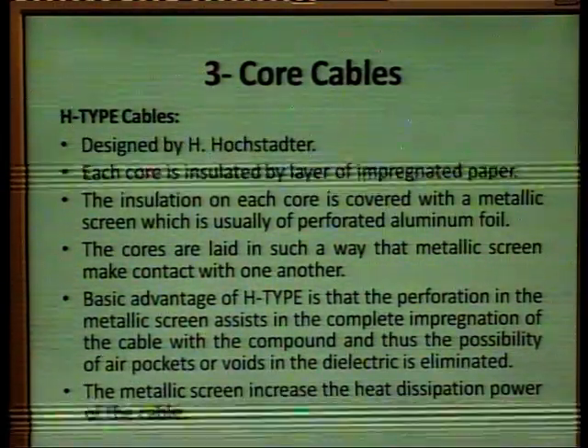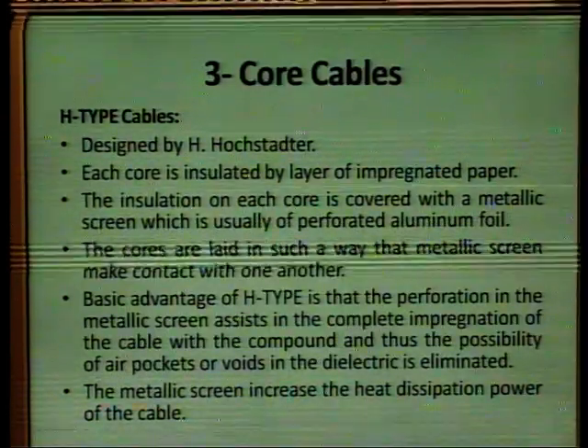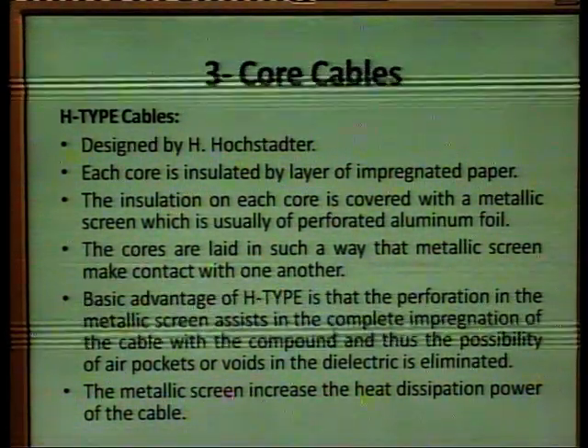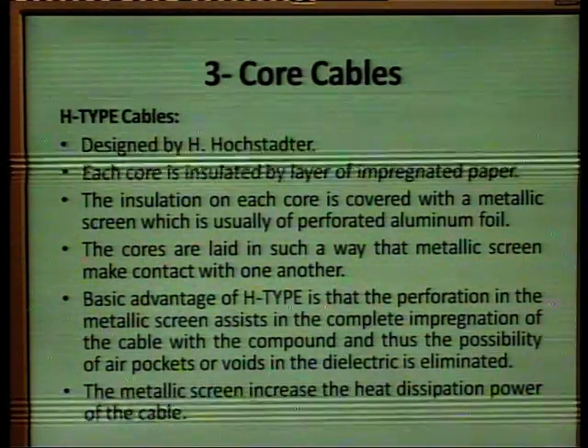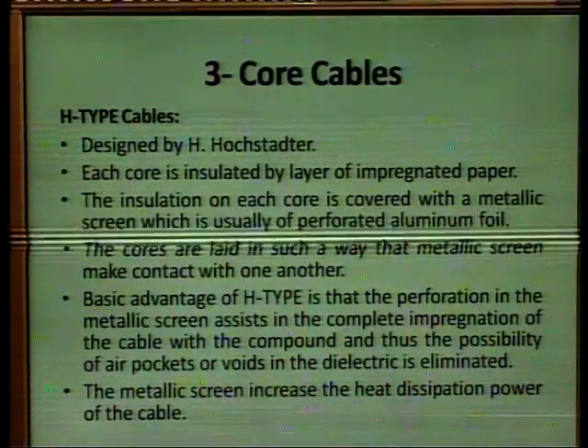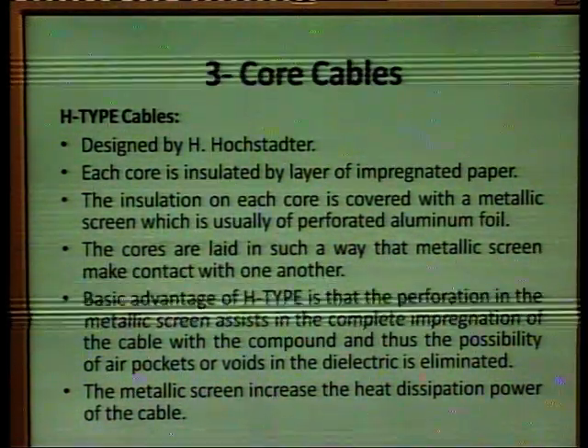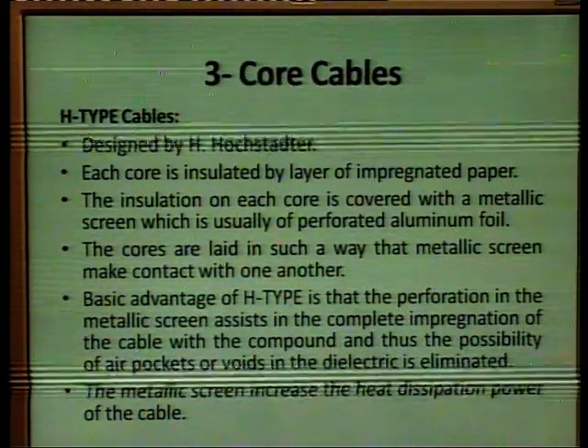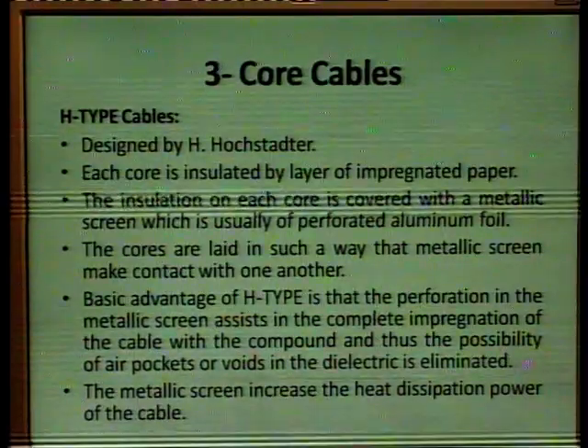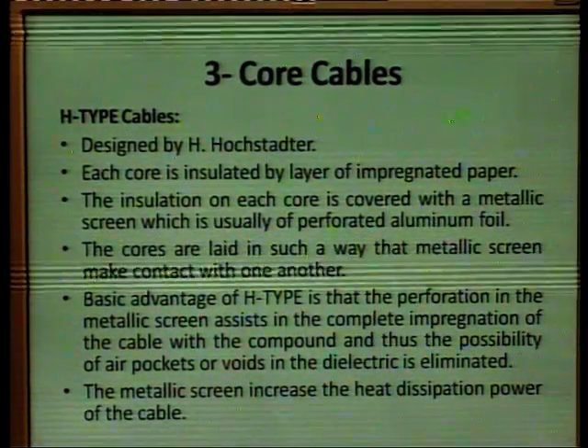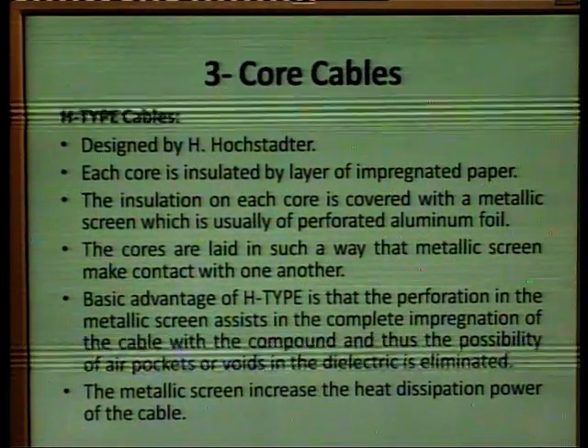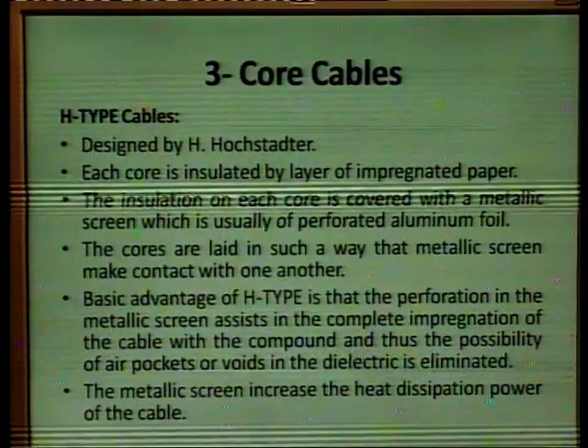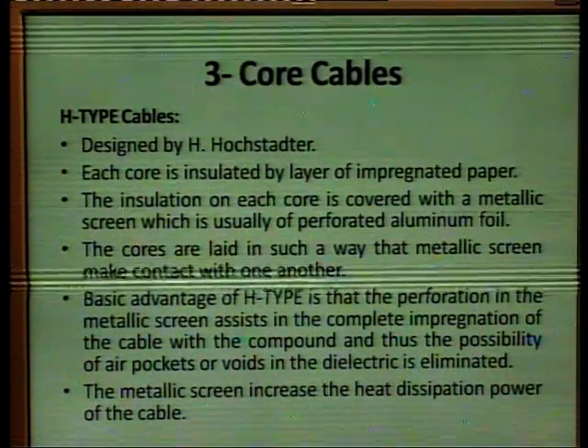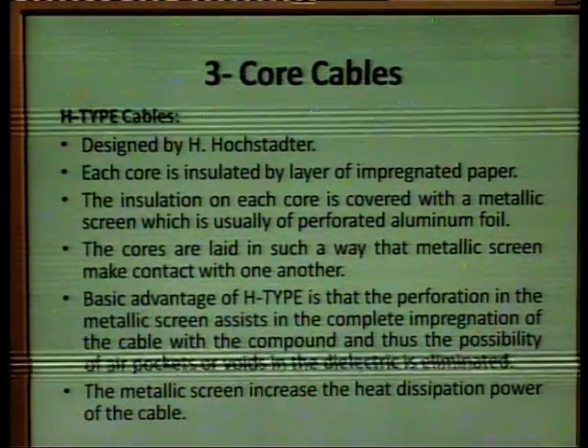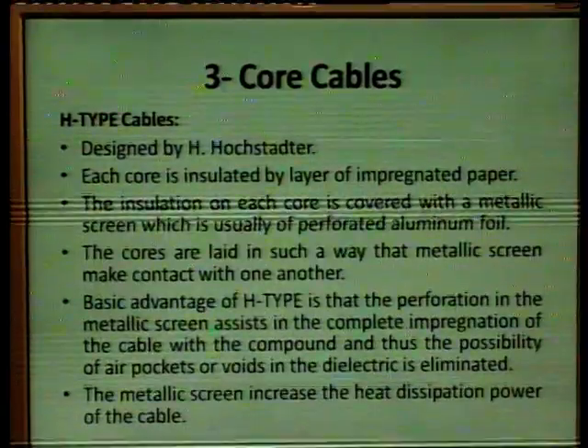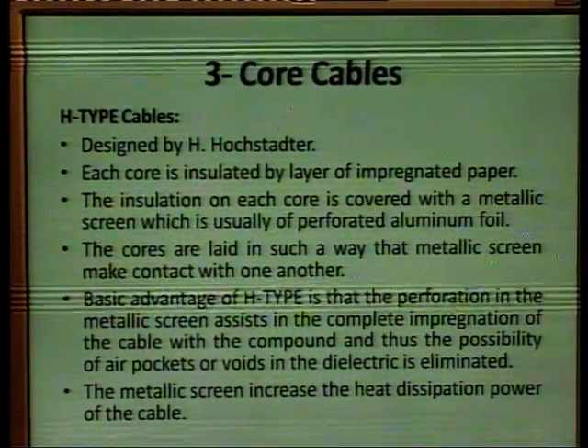H type cables are designed by H. Hochstadter, and each core is insulated by a layer of impregnated paper, and the insulation on each core is covered with a metallic screen, which is usually of perforated aluminum foil, and the cores are laid in such a way that the metallic screens make contact with one another.